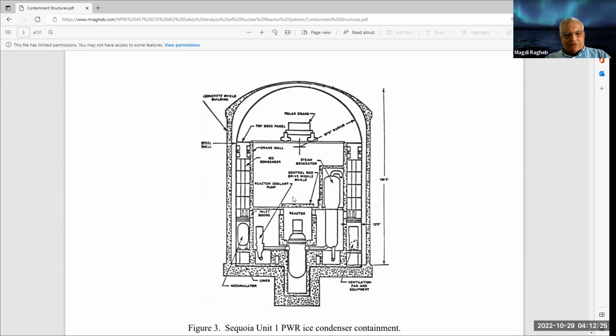Why ice? Because if, say, an earthquake happens and you lose some of the piping, it breaks here, the coolant will be lost. It flashes into steam. That containment would now contain steam at high pressure, and the steam would be quenched or condensed in the ice that's inside the containment itself. This is part of the design because, in fact, the concrete structure that surrounds the steel shell acts as an insulator. It does not allow the heat that is in the steam released inside the containment to be released to the environment.